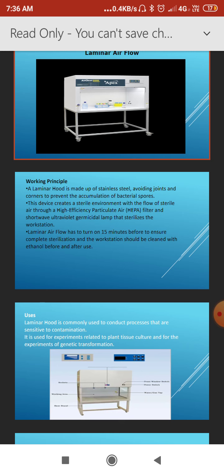The laminar hood is made up of stainless steel, avoiding joints and corners to prevent the accumulation of bacterial spores. This device creates a sterile environment with the flow of sterile air through the high efficiency particulate air — that is the HEPA filter — and a shortwave ultraviolet germicidal lamp that sterilizes the workstation.